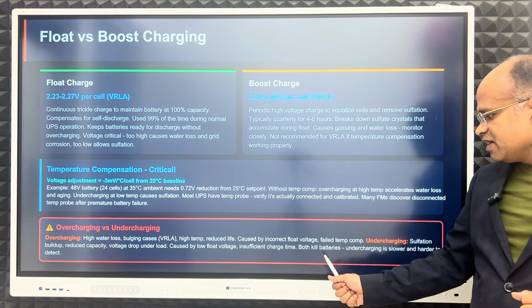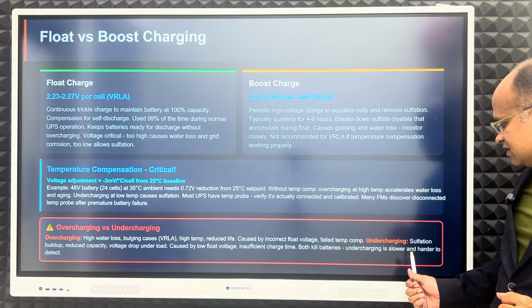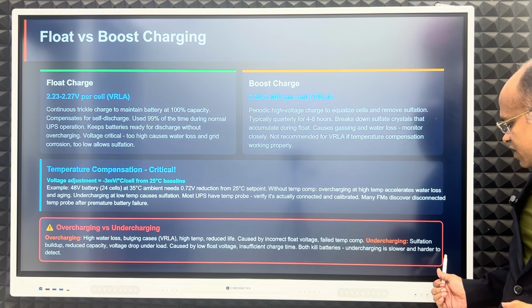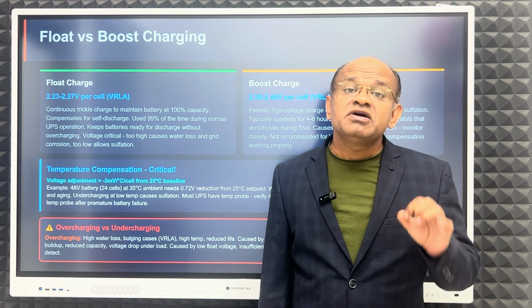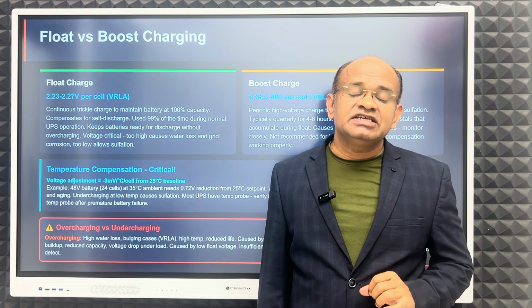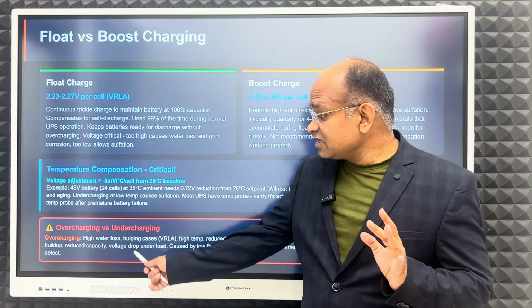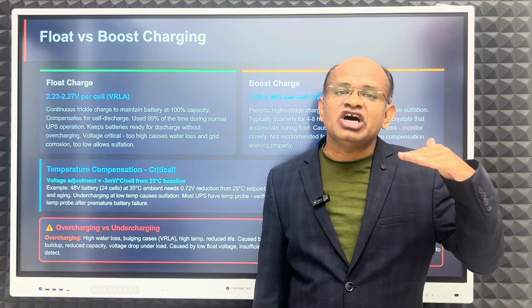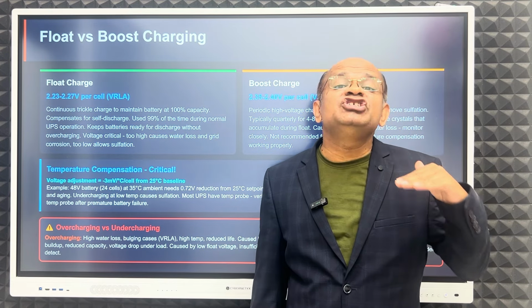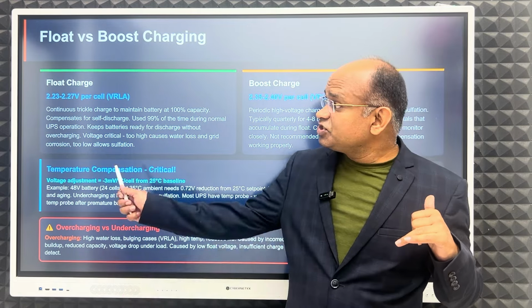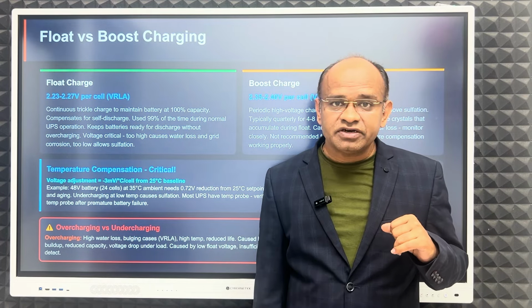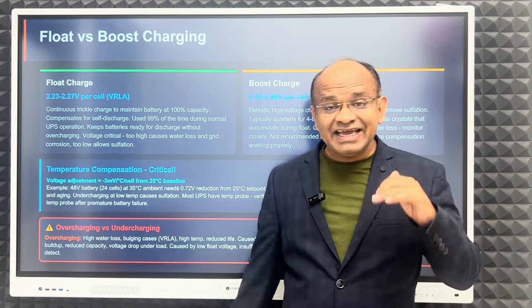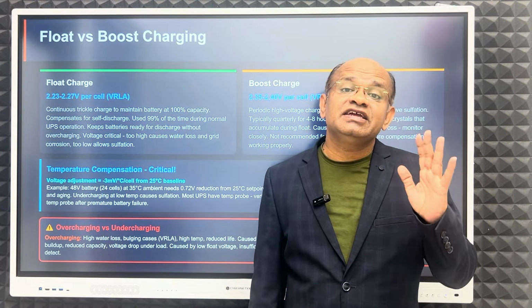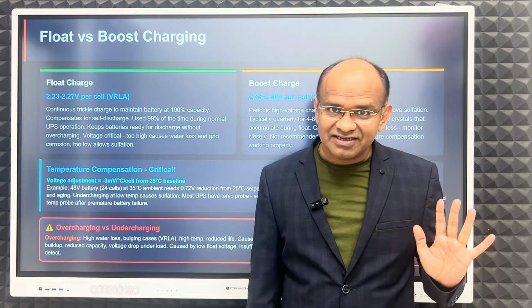Insufficient charge time: both kill batteries, but undercharging is slower and harder to detect. So overcharging and undercharging are both killers of the battery. Just note this down. This is very important. We should understand that it should be optimized, precise charging. So check with your UPS vendor or battery vendor what the exact charging current is and whether it is being applied or not.